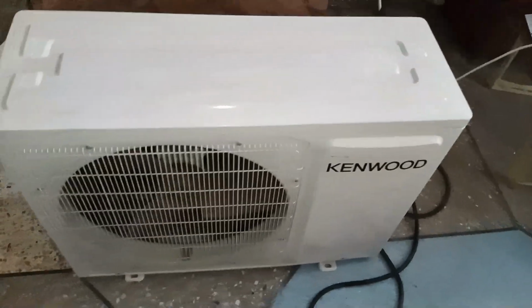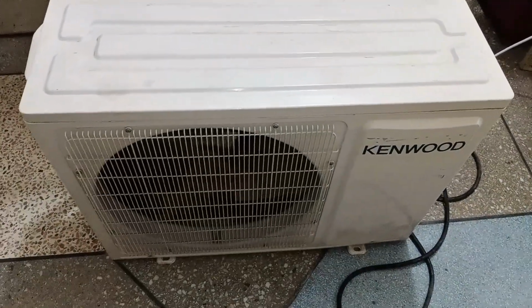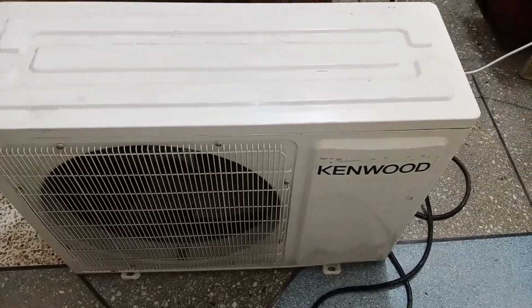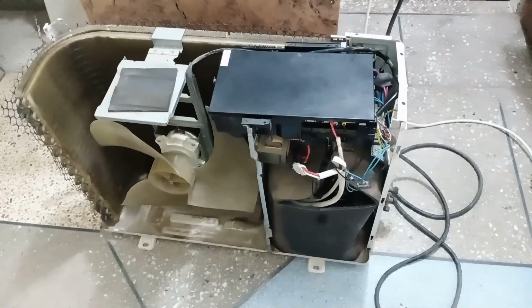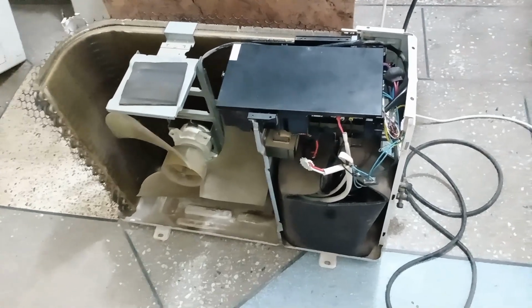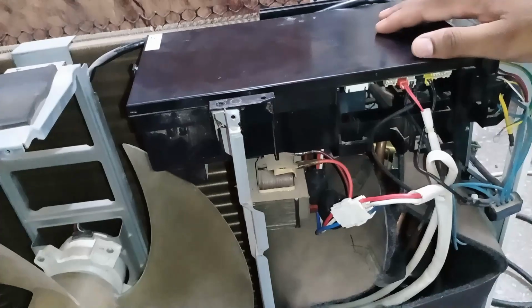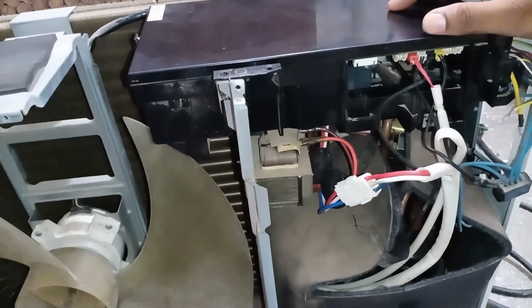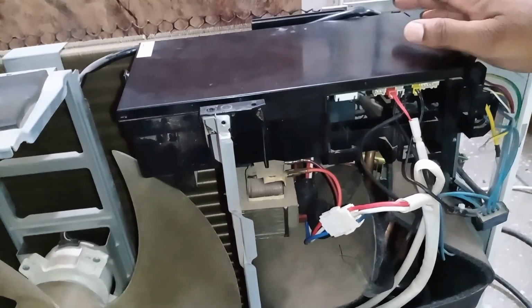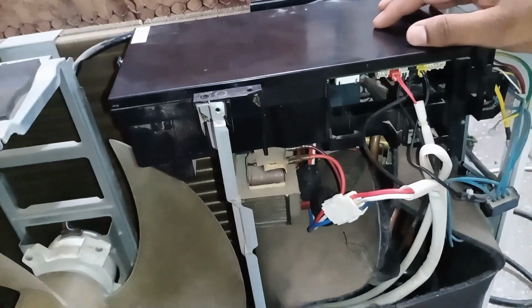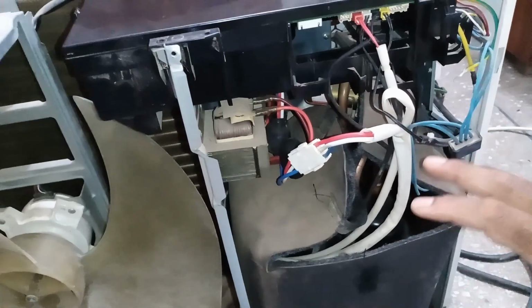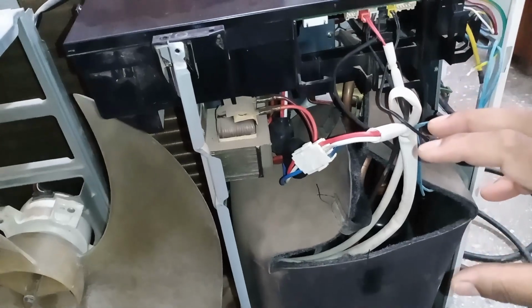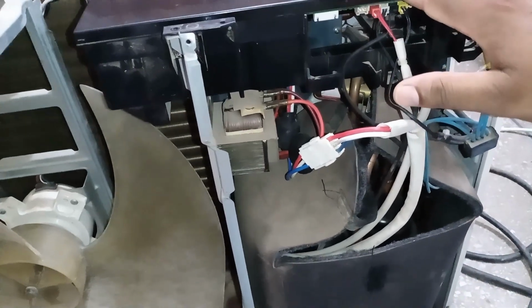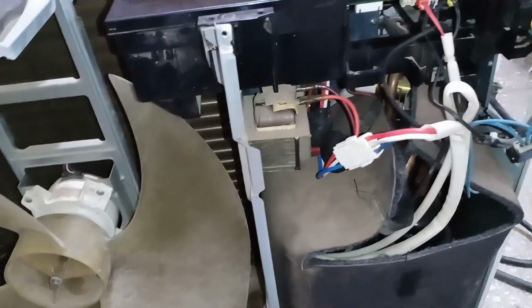Since this error is related to the outdoor unit, we will now check the outdoor side to diagnose the issue properly. I have completely removed the cover, and now you can see the fan and the outdoor PCB. This is the main outdoor PCB, and in technical terms, we refer to error 19 as an outdoor main PCB drive error. This error occurs when the outdoor unit's compressor does not start or does not run. When this happens, the unit will display error 19. Possible causes of error 19.